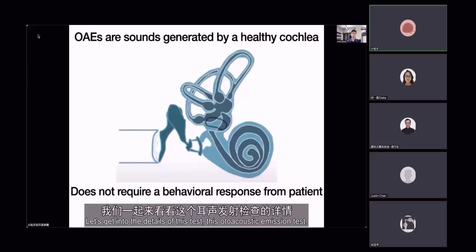So let's get into the details of this test, this otoacoustic emission test. Although conventional devices are pretty expensive, the principle of operation here really only requires a pretty simple setup. It only requires 2 speakers to send a sound stimulus into the ear and a single microphone right by the ear tip to record the response.